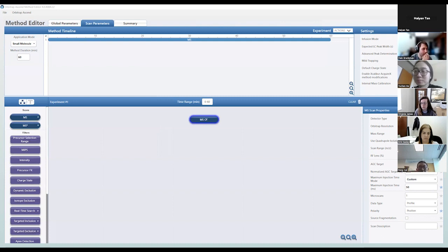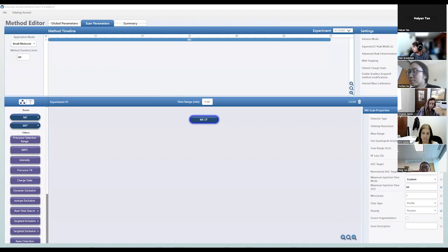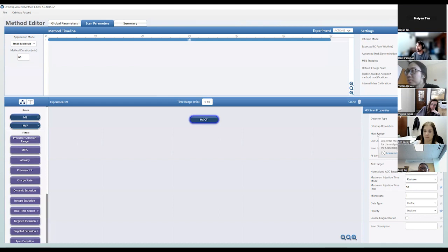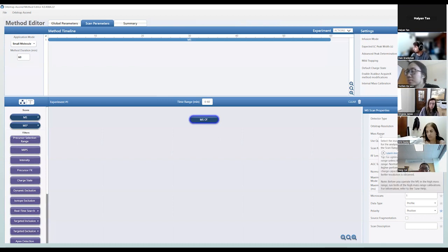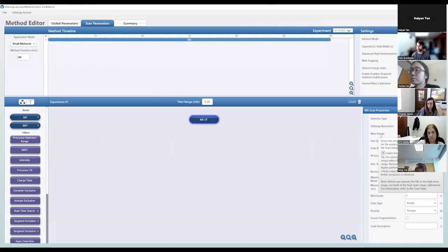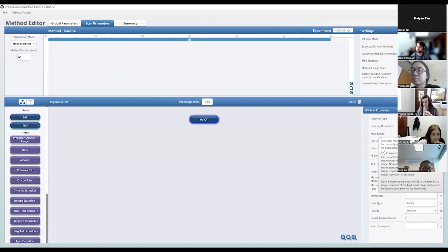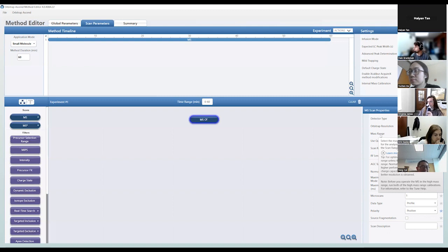Haiyan asks about the difference between mass range and scan range. Mass range basically changes the electronics — setting it to high mass range means you can't scan as low as usual. It's more for intact proteins, middle-down, or top-down analyses where you have multi-kilodalton precursors. For normal lipid analysis you use normal mass range and then specify your scan range, e.g., 200 to 1600.